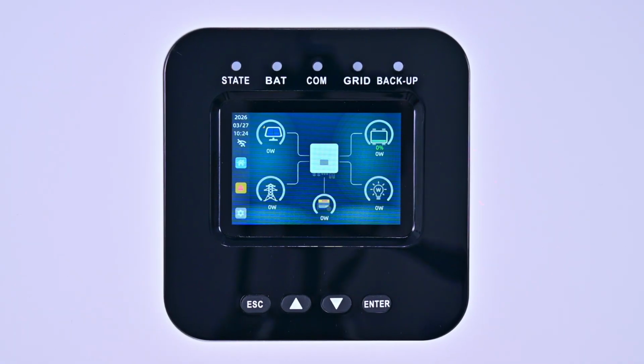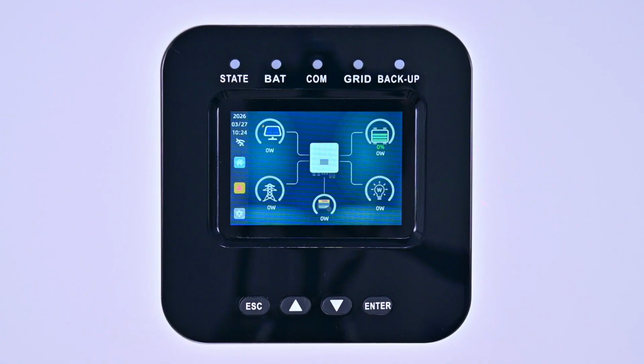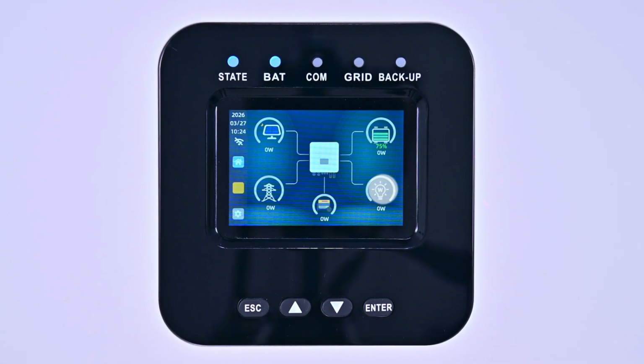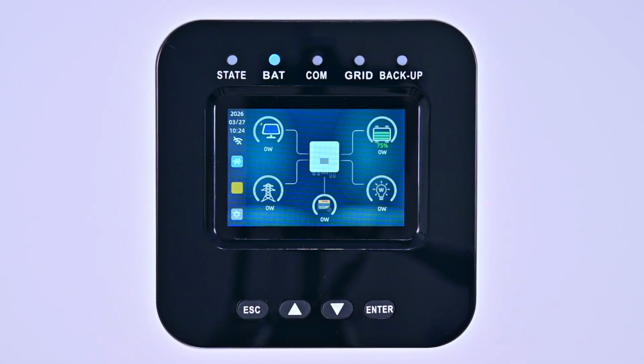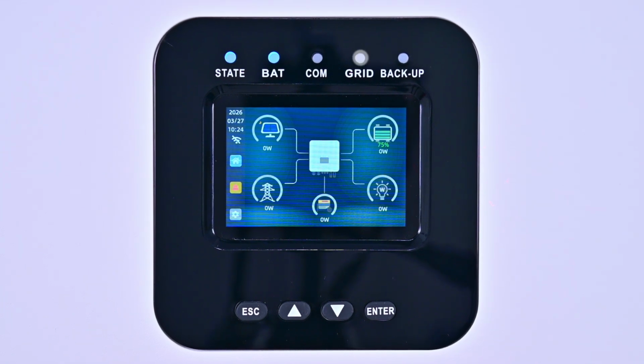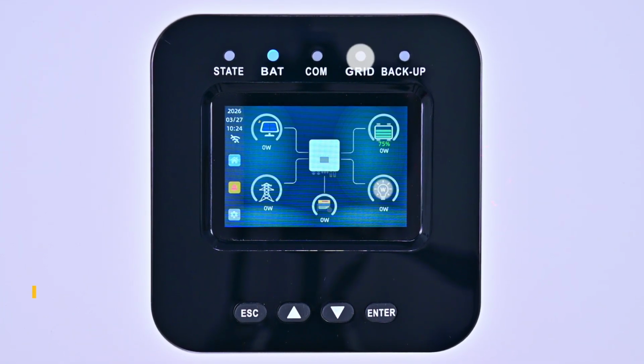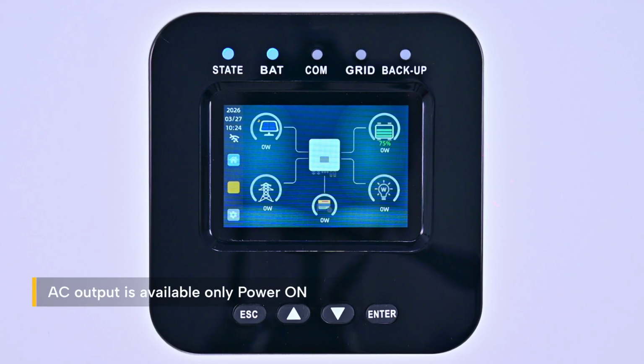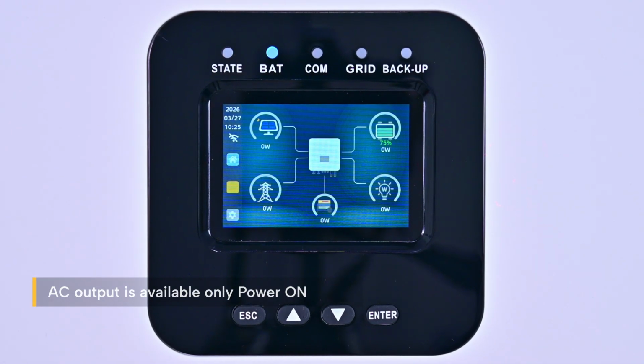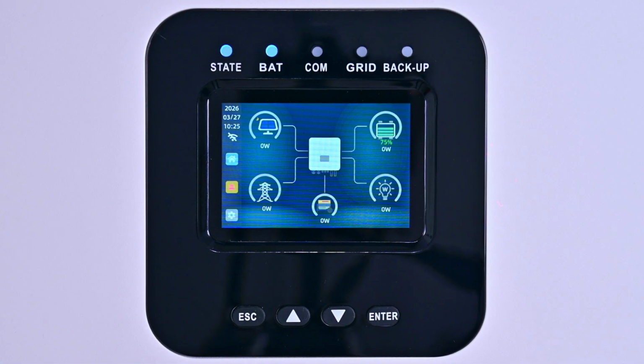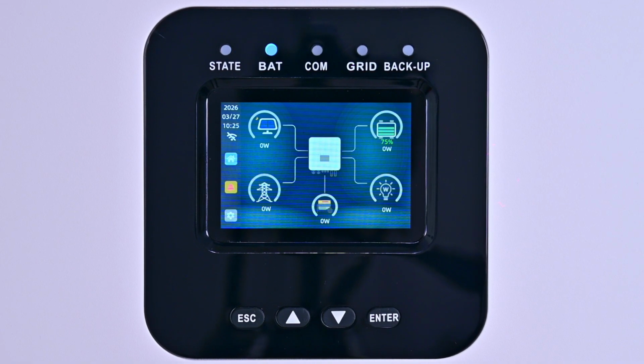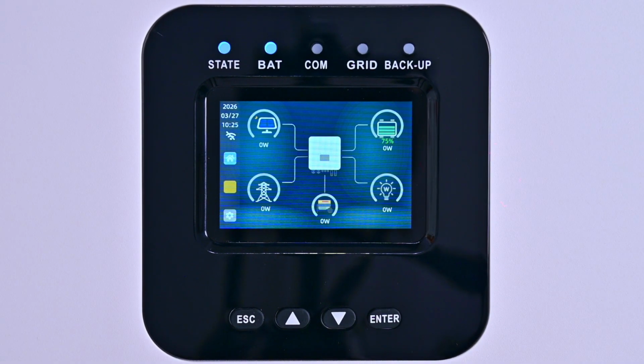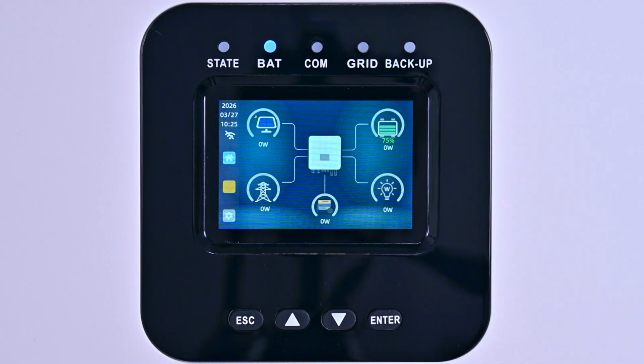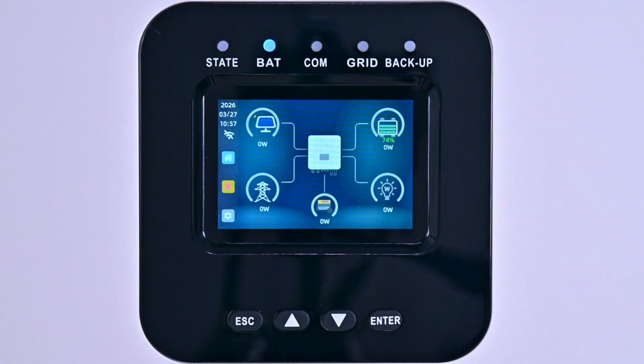We are now at the system's main interface. Although the device screen is lit and can be configured normally, the AC input and output ports have not yet been activated. We must enter the operating system to power on the device. We designed it this way so that you power on the device only after completing as many settings as possible, ensuring the cleanest possible current is supplied to the load and the grid.